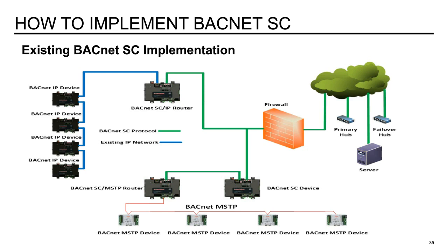So that's the real advantage of BACnet SC. I hate to keep pointing back to this slide that's on the screen, but if you've got existing BACnet MSTP devices or existing BACnet IP devices, you can put in a BACnet SC router. So in the case of what's on the screen for the IP devices, you can put in a BACnet SC to IP router, and then all of the devices that are behind or downstream of this router would be connected through BACnet SC and have the BACnet SC security from the router out.